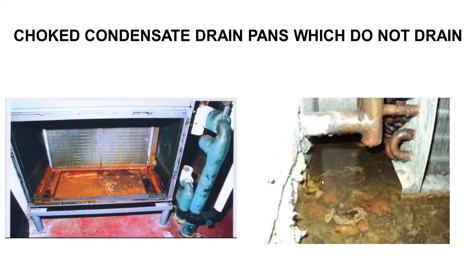Then you've got the fresh air duct, and if you think that this is all cooked up, you'll find a newspaper item where one of the hospitals, that was KEM Hospital orthopedic area, they had to close the OT for orthopedic operations for 3 days because there was a dead pigeon in the fresh air duct, and that smell coming. They went and did some investigation, and this is what they found. So it is not that it happened just overnight. This must have been going on for quite a few days, and it was then realized that there is a dead pigeon out there, and it is not a one-off thing. This happens all the time.